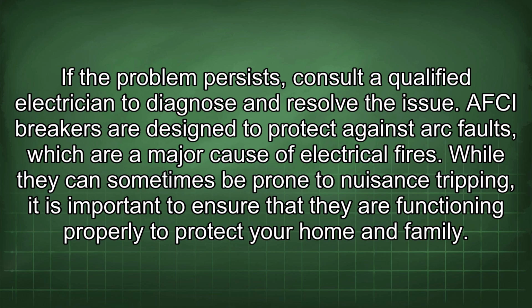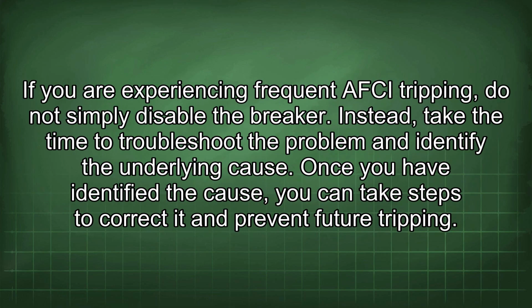AFCI breakers are designed to protect against arc faults, which are a major cause of electrical fires. While they can sometimes be prone to nuisance tripping, it is important to ensure that they are functioning properly to protect your home and family. If you are experiencing frequent AFCI tripping, do not simply disable the breaker. Instead, take the time to troubleshoot the problem and identify the underlying cause.